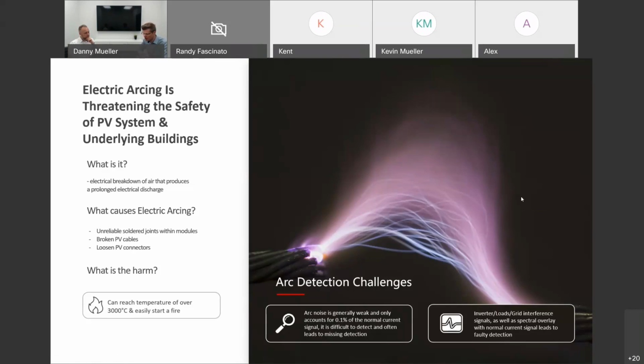And a lot of that stuff got resolved, and we can talk a little bit about what Huawei is doing about it and what the causes typically are for these arc faults versus a fault trip based on an arc fault message. So the most common root cause for an arc fault in a system actually is the connectors of your DC system. A lot of installers may be in a rush and they don't pay too much attention to how the crimp is actually done to have the right connectors. The matching connector requirements we have today are really a result of that early issue scenario. And my recommendation is to pay a lot of attention for your team and your installation crew to really take your time for a proper crimp and a proper tightening of the grommet at the end of the connector.